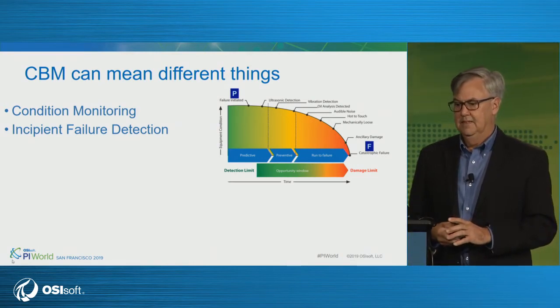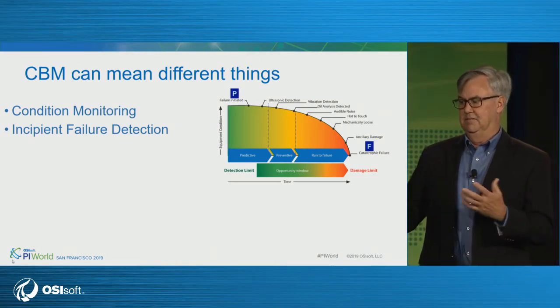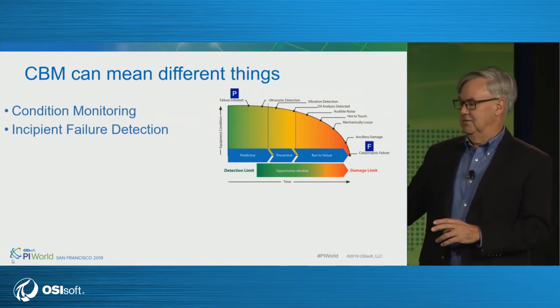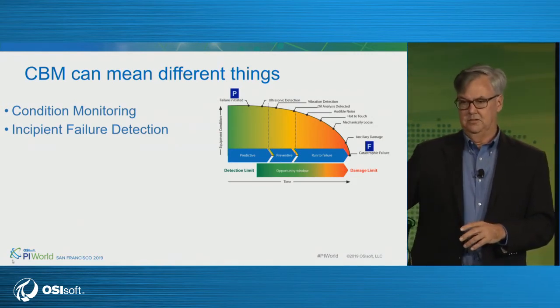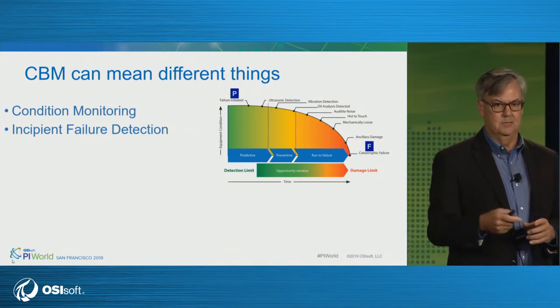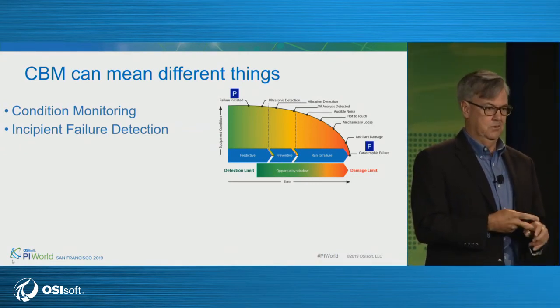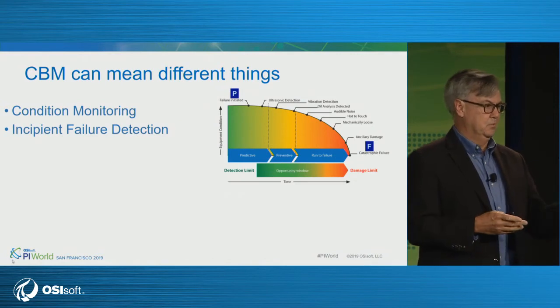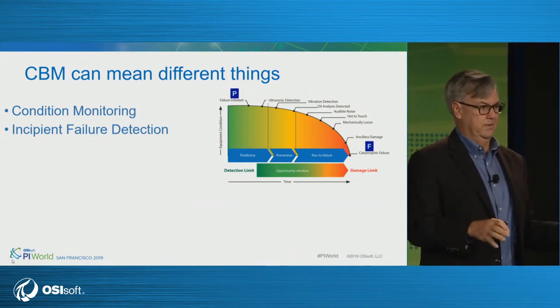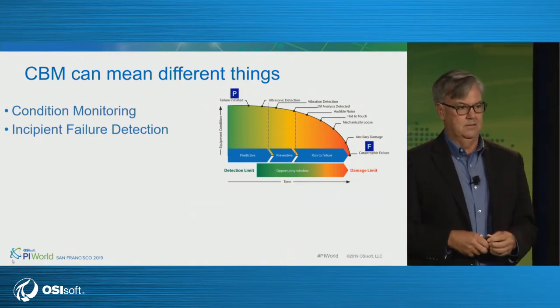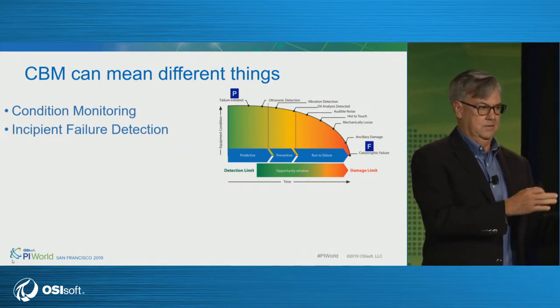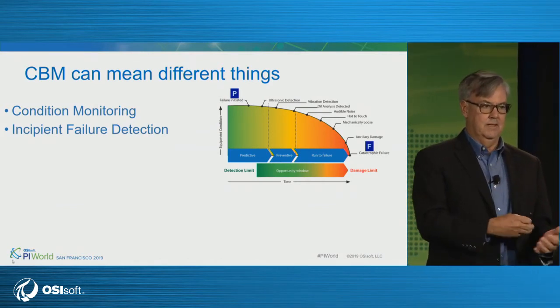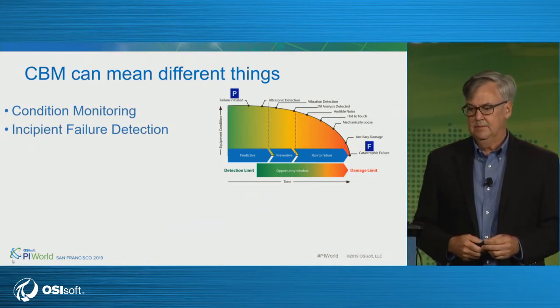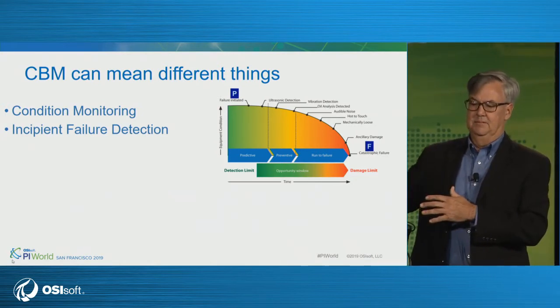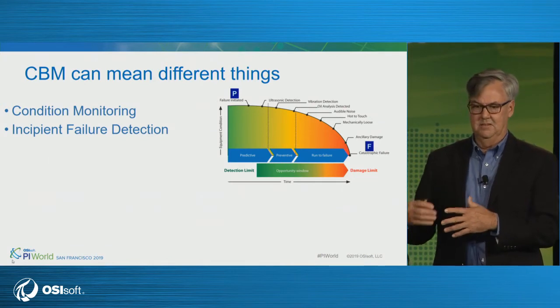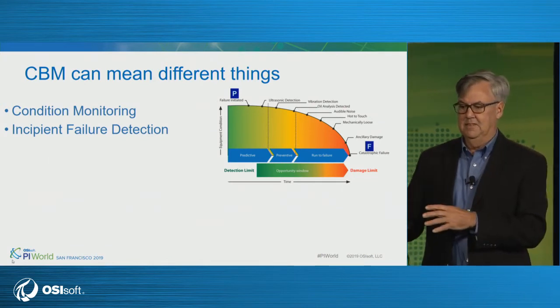In maintenance circles for decades, we've called these predictive technologies or predictive maintenance: oil analysis, motor current signature analysis, vibration monitoring. It's usually not about the operation of the asset, but about its condition. Based on certain profiles from those diagnostic tests, I can better predict when the asset is going to fail.